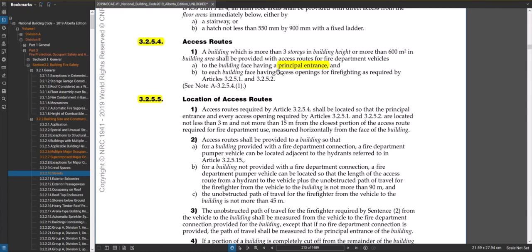There are cases where you have a mall or something with multiple principal entries, but you would only identify one as the principal entry for fire department purposes — that's the entry they'll go to if there's an alarm. I've worked on some big box strip mall type buildings where every tenant had a principal entry, so there might be eight of them across the length of the building. In that case the local fire department said to put a room on the back side and call that the principal entry, so they knew to go there first.